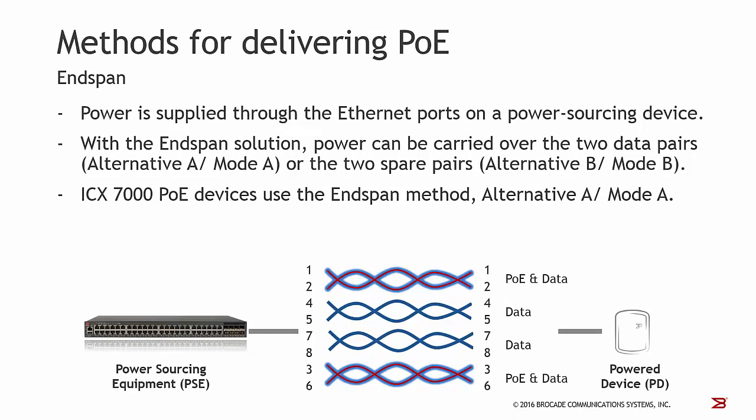The second method is called Endspan, where power is supplied through the Ethernet ports on a power sourcing device directly. Endspan supports two modes: Alternative B or Mode B, just covered in the Midspan technology, and Alternative A or Mode A, where power can be carried over the two data pairs of wires. Mode A is also supported on all ICX 7000 PoE devices.